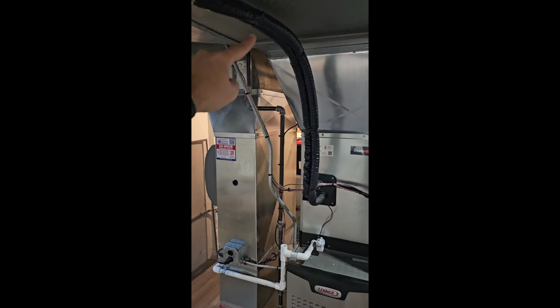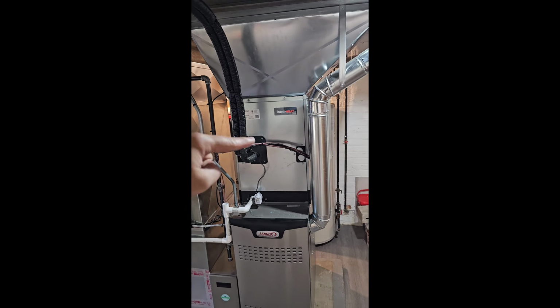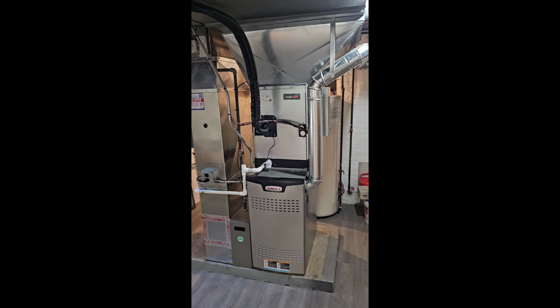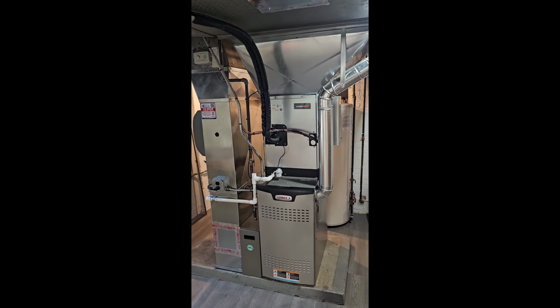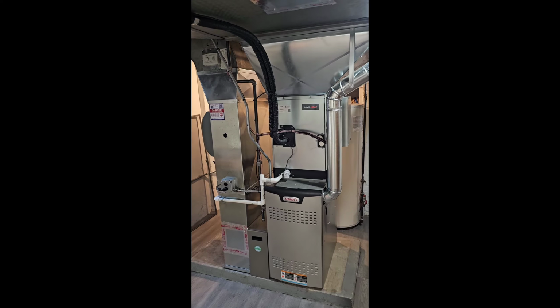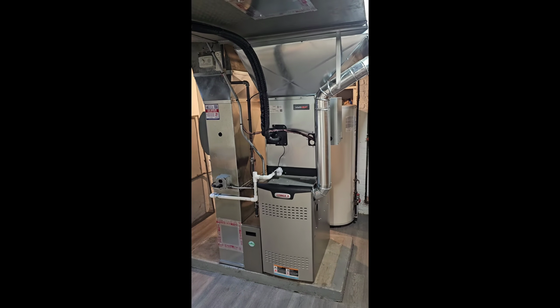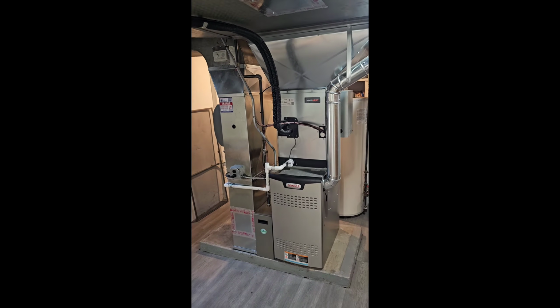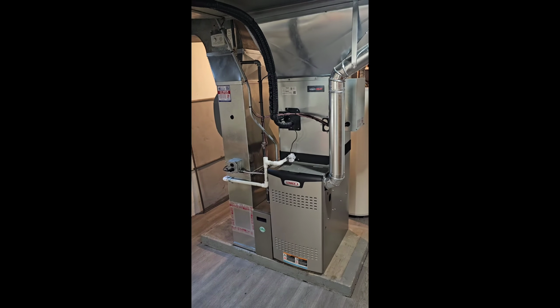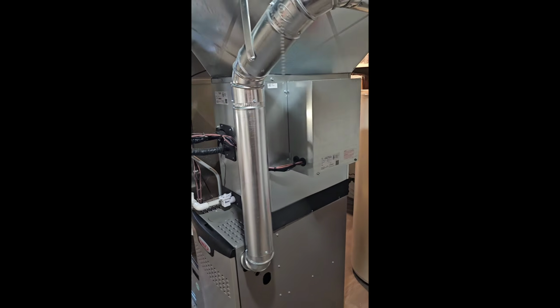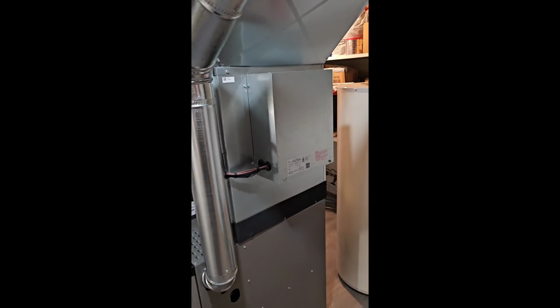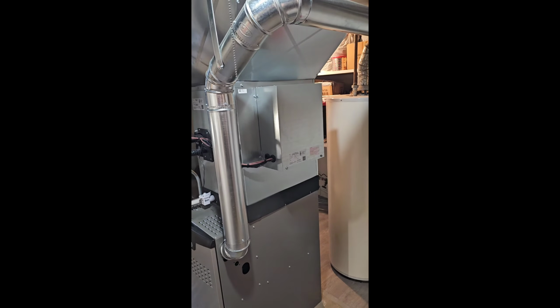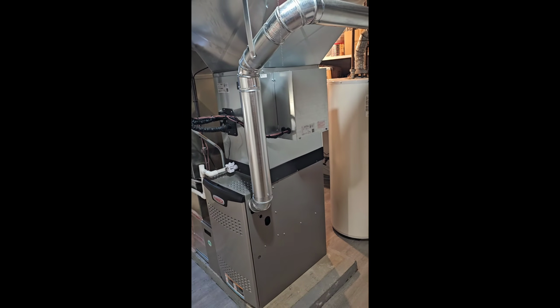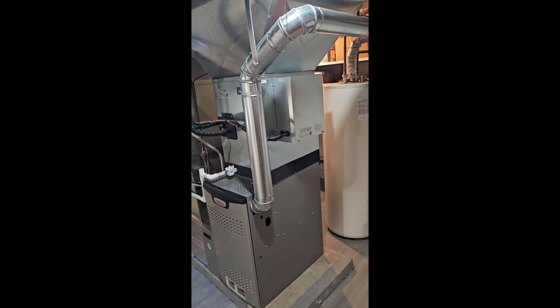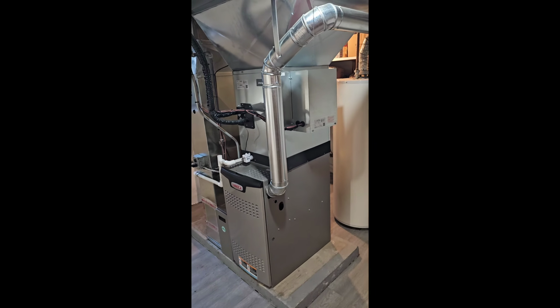The same applies when the unit is running on cooling mode. Our outdoor unit is going to be bringing cold refrigerant, making the coil very cold, and the furnace will blow air across it, giving cold air through the home, with the big difference being variable speed air conditioning, so very stable temperature control. And all this happens seamlessly, automatically, thanks to our Mitsubishi IntelliHeat control box. This is going to be doing all the intelligence to decide whether to run the heat pump, the furnace, or the air conditioner. All the homeowner needs to do is set the thermostat, heat or cool, at whatever temperature they choose, and the system will figure out the rest.